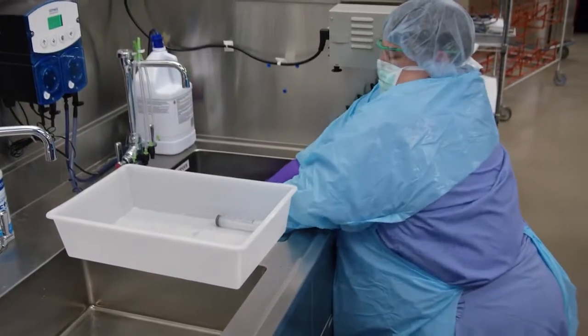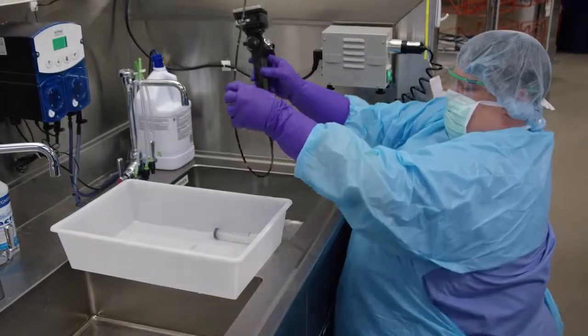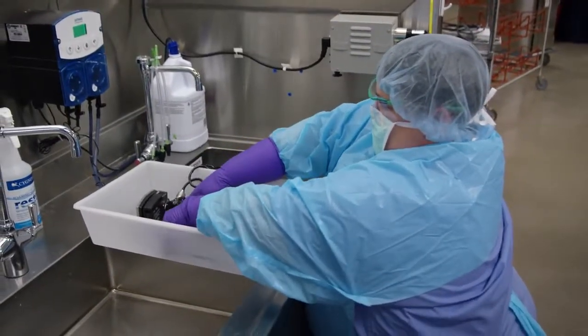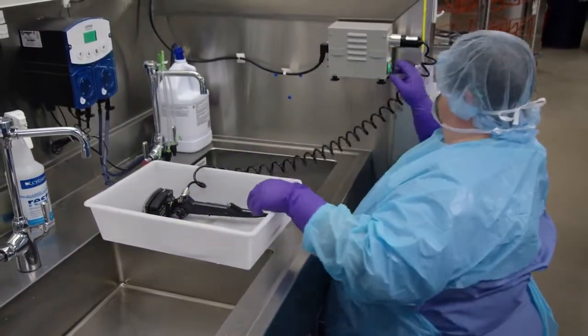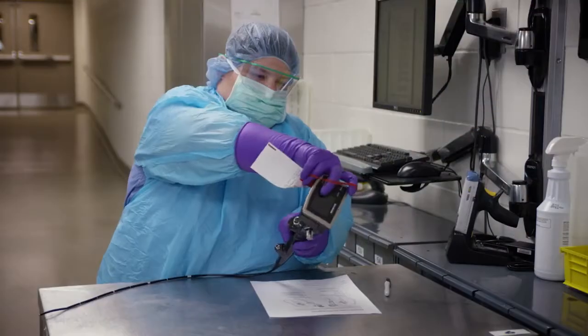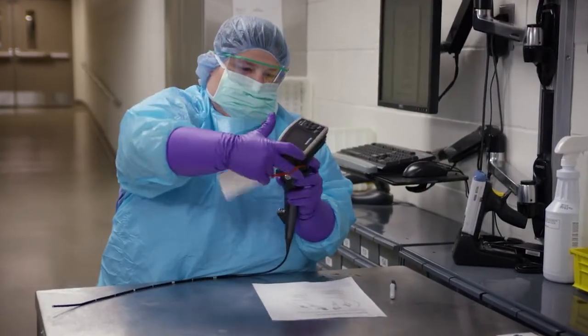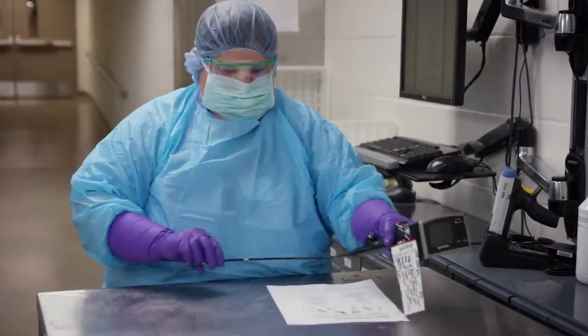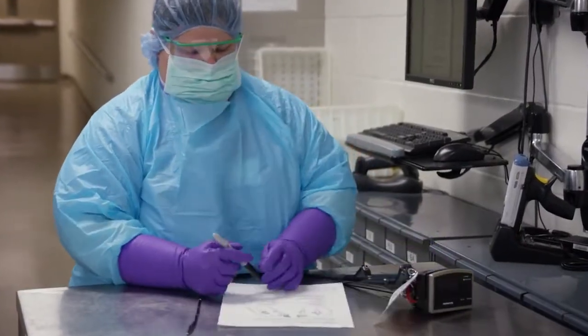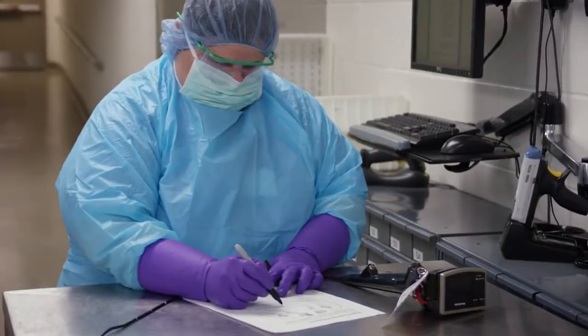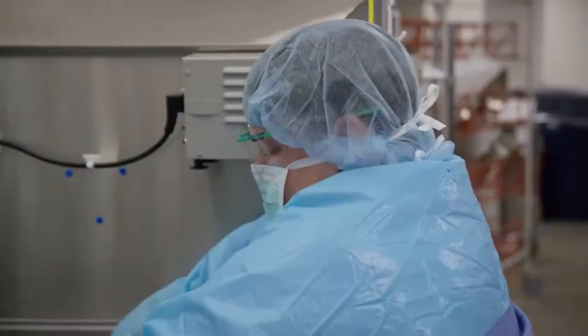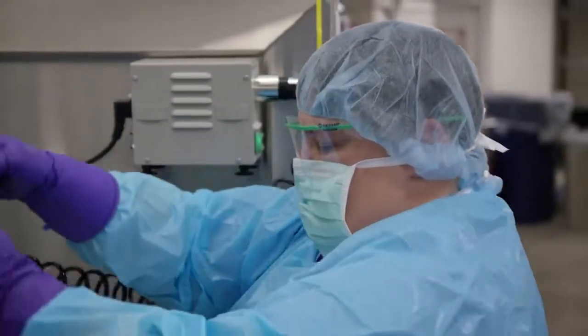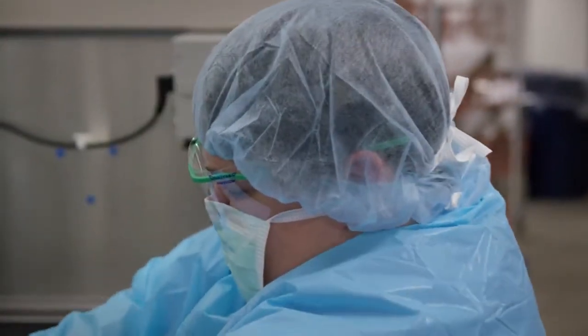If a leak is detected, the leak testing device should remain attached to the endoscope and under pressure until it is removed from the water. Tag the scope for repair and follow manufacturer guidelines for proper cleaning and high-level disinfection before returning it to the repair facility. If the endoscope passed the leak test, remove it from the water and drain.